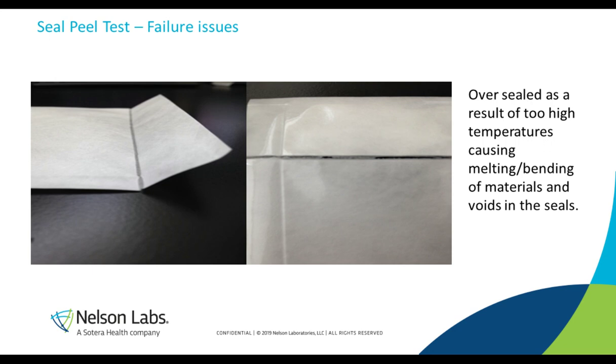A couple things on seal peel failures. If you overseal, for example, this is a Tyvek pouch, you will get this clarifying of material. It can have detrimental effects to the pouch. Now, I've heard in the past that, well, if it's clear, that just means it's sealed really good, which is really not the case. What happens is you've actually melted the material and you actually do get voids, and you've actually damaged the packaging. So oversealing is listed in the visual inspection as something that you do not want to have.